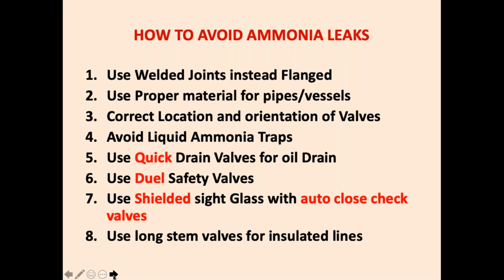Avoid liquid ammonia traps. Use, very important, not an ordinary stop valve. Use a quick drain stop valve for oil draining. What is a quick drain stop valve? When you, by mistake, release your hand, the valve will close automatically. Many times accidents have taken place because the operator has opened the ammonia valve quickly and a lot of liquid has come out. He has run away and the ammonia has been leaking in the plant. So this is important.